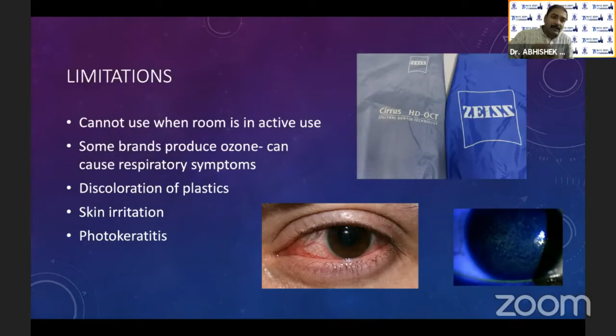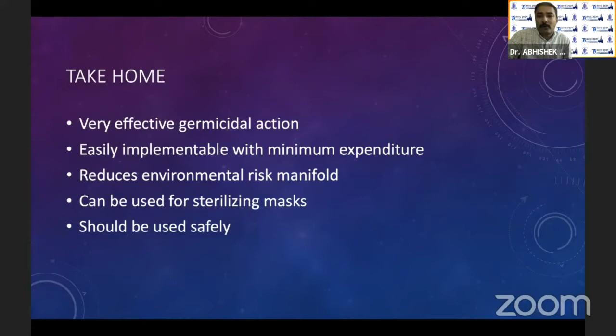So these are the limitations of UV light, but otherwise it's a fantastic way. Don't go for these handheld instruments, these handheld lights which people wave. There is something called a contact time which is required. So fixed devices which stay without moving for at least 10 to 15 minutes are useful. UVC has very effective germicidal action. It is easily implementable with minimum expenditure. It also reduces the environmental risk of our exposure, and can be used for sterilizing masks. But be careful not to expose yourself for long, because otherwise you have a very painful day ahead. Thank you so much.